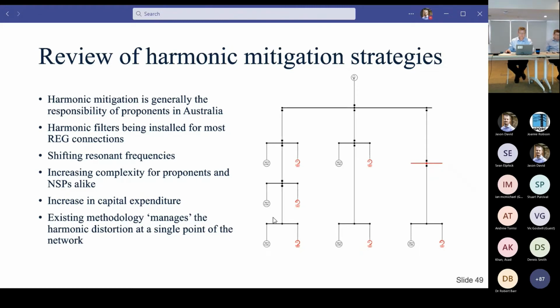The reason this is important is that the methodology currently applied requires harmonic mitigation at the point of connection for individual generators, as Sean mentioned previously in response to some of the questions. This provides a low impedance path for harmonic current to flow, stopping that current from flowing out into the network, hitting a large impedance and creating an amplification of harmonic voltage. Theoretically and fundamentally, this all works out. It makes sense. But in practical application, there are particular complexities that perhaps aren't being thought about in much detail.